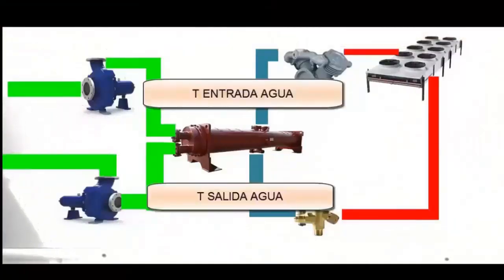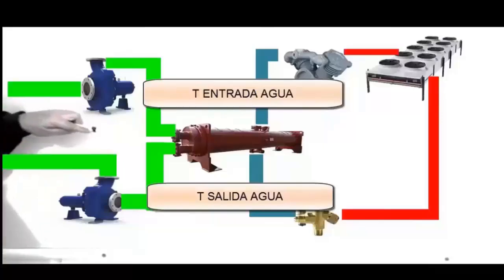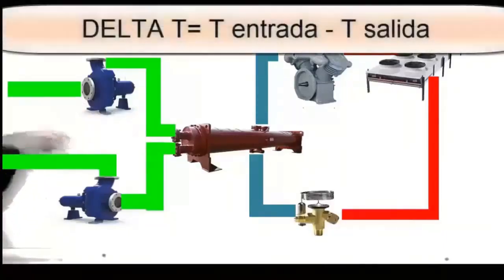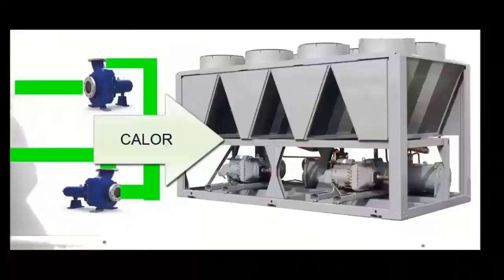This temperature differential is a crucial indicator of the system's efficiency and is especially relevant in air conditioning applications, where the delta T is usually about 5 degrees Celsius or 10 degrees Fahrenheit. A higher delta T indicates greater efficiency in the heat transfer process.